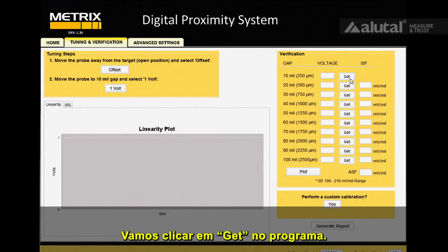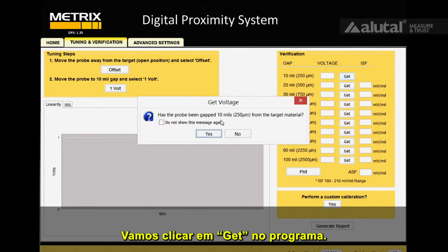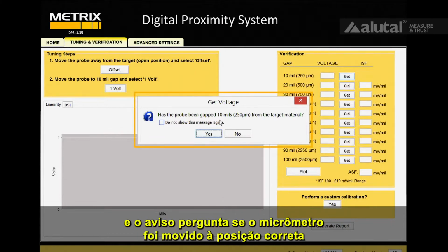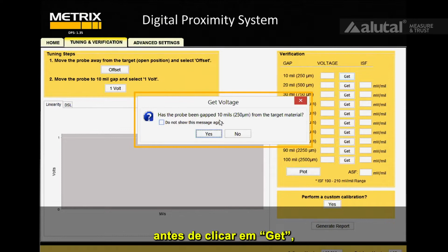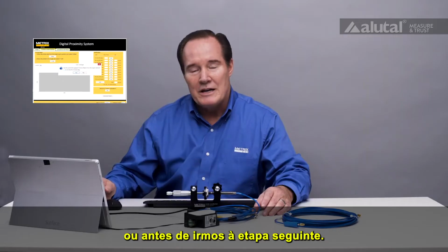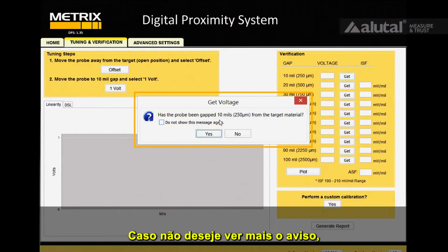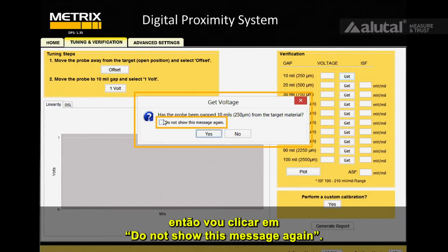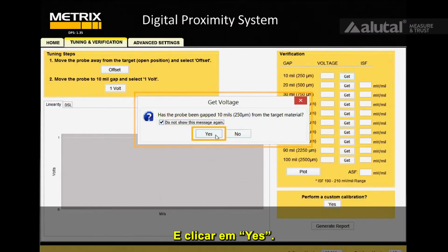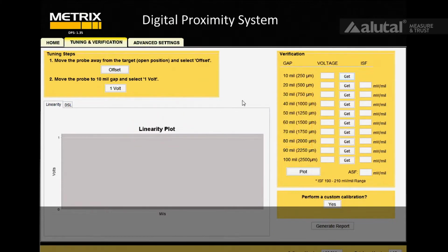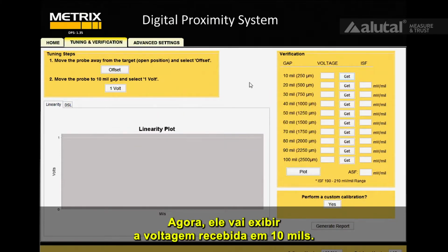And then we say get on the software. It comes up with this warning each time, and the warning basically says, have you moved the micrometer to the right position before you hit get, or before you go to the next step. So I don't need to see that warning anymore, so I'm going to go ahead and say, do not show me the warning. All right, and I'll say yes. And now it will fill in with the voltage that it sees at 10 mils.